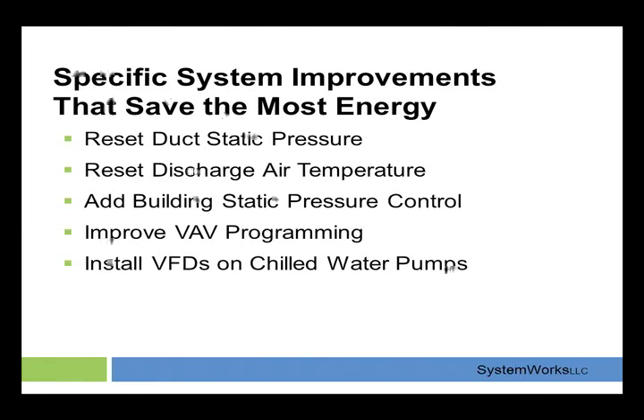Reset duct static pressure, discharge air temperature, and what that means is as the building or the school or whatever the application is, as the space calls for cooling, the VAV boxes or the spaces open up and they try to deliver more cool air to the space. And what we do is the control system has the power to look at all of that and analyze, hey, my building's calling for cooling, let's put out cooler air from the main unit that serves that building. And the inverse happens on a heating call.